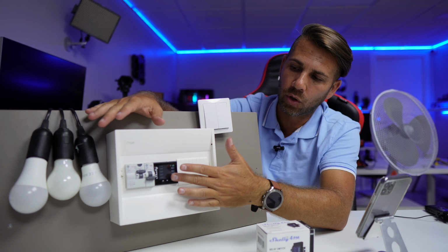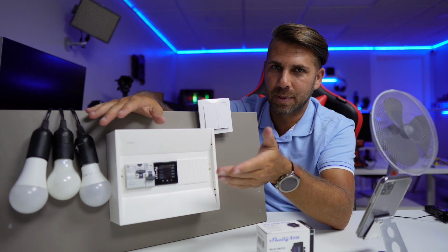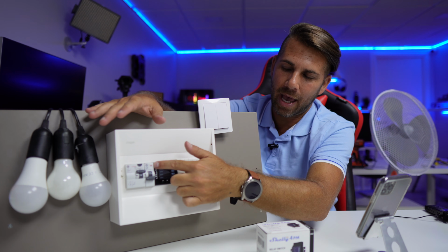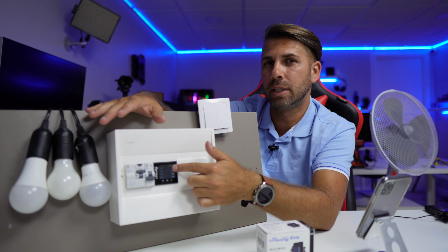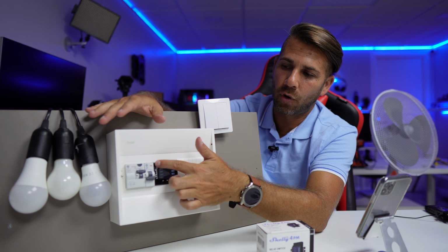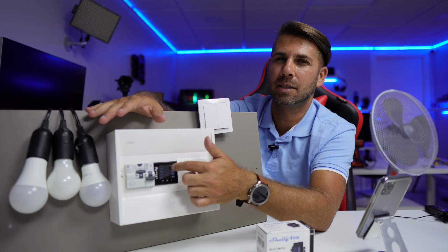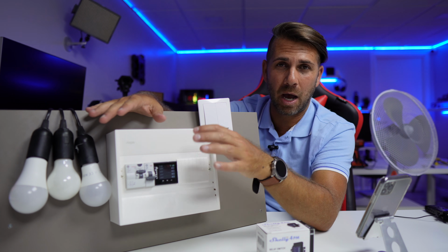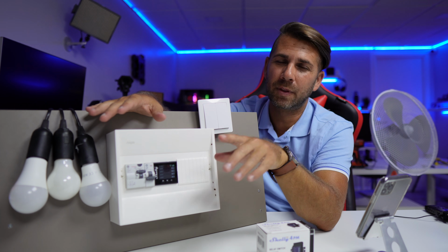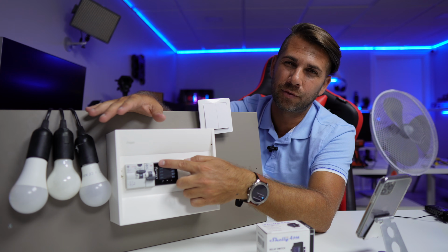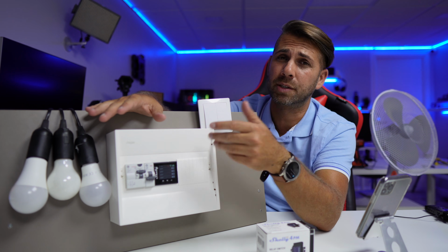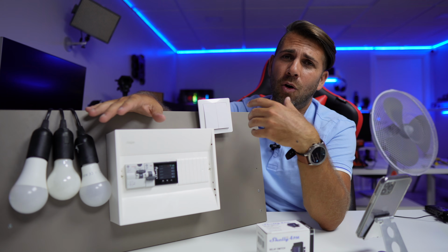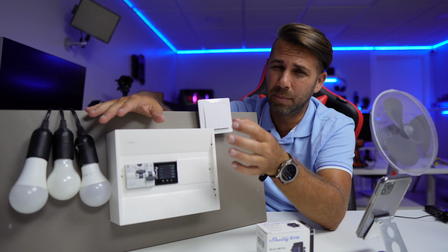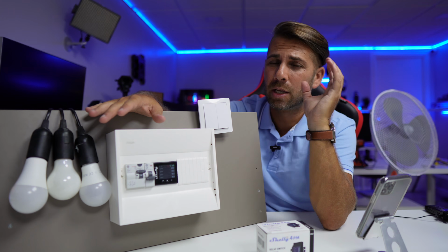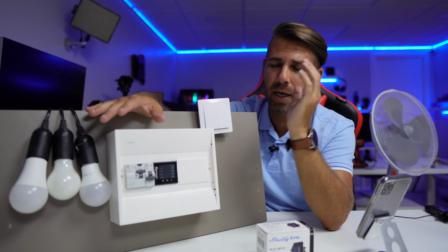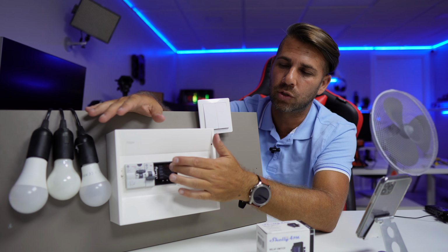For those not very familiar with amps and watts, this has a total capacity of 40 amperes, and for every single output it has 16 amps of maximum output. This means roughly a maximum capacity of 3,500 watts, which is a lot. We'll be able to put any of our regular devices to work. This information is important so you can make your calculations and decide which device you want to connect to each one of these.